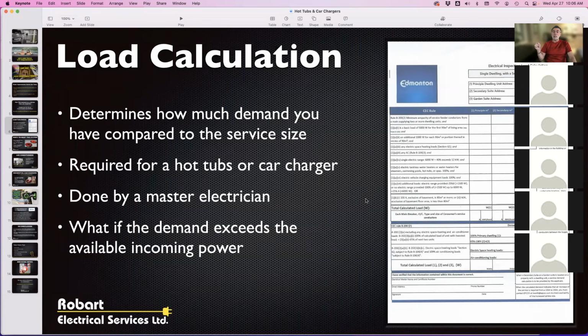What the load calculation does is determine how much demand you're putting onto this service, and it will tell the city if you've exceeded your service. Now, this is taken out by a master electrician, and there's usually a fee for this, for the calculations and so forth, because when we put our name at the bottom with our master electrician number, that means we're taking responsibility.